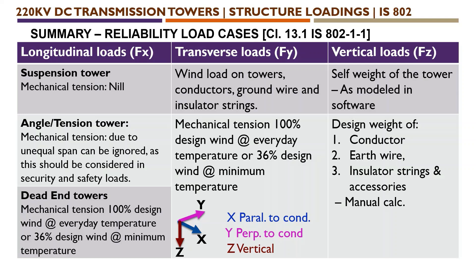There are 3-dimensional forces we need to calculate. The first is longitudinal loads. For a suspension tower we should not consider any mechanical tension. For an angle or tension tower, whether to consider mechanical tension depends on the case, but due to unequal span we can generally ignore mechanical tension, as it is already considered under security or safety loads under a broken wire condition.